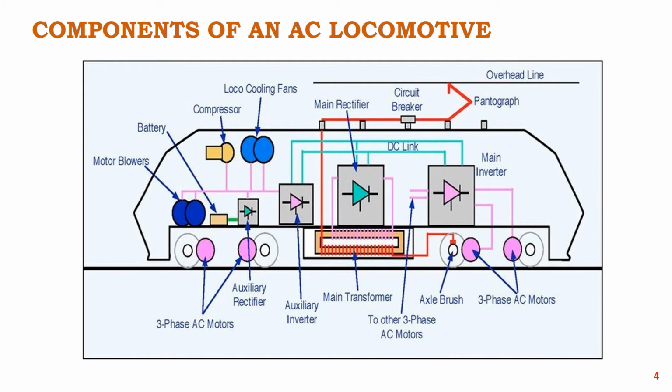And one of the very important motors used in traction system is three phase induction motor. It provides a constant speed operation, developing low starting torque, drawing high starting current, and complicated control networks make it unsuitable for electric traction work. Automatic regeneration is the main advantage in electric traction with the motor.